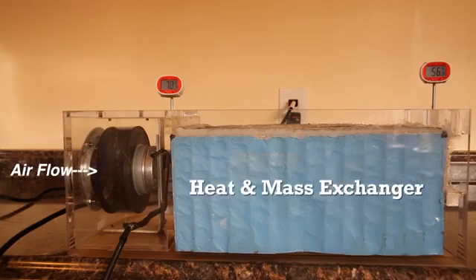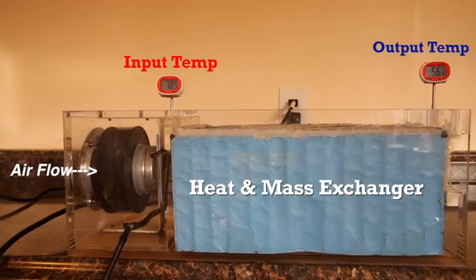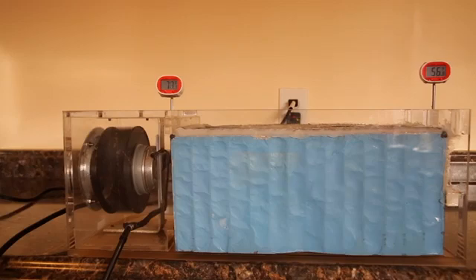As you can see, the fan is pushing the air through with an inlet temperature of 78 degrees and an output temperature of approximately 57 degrees. That's 20 degrees of cooling without use of any mechanical refrigerants or chemical components.